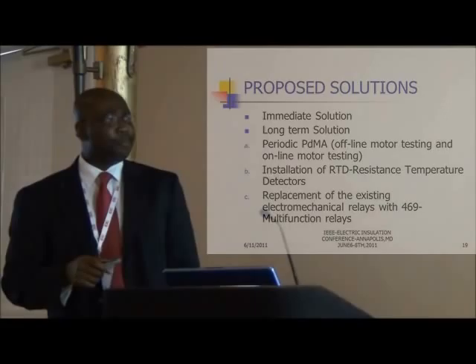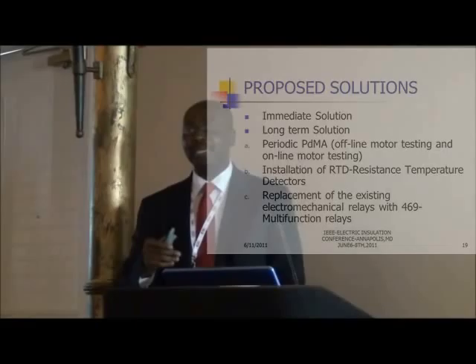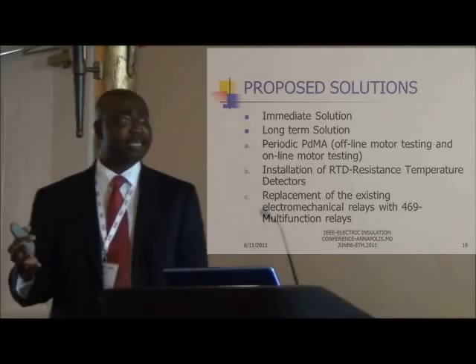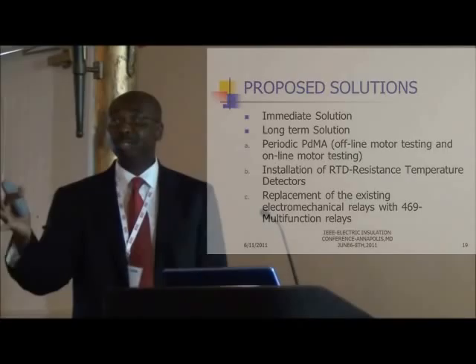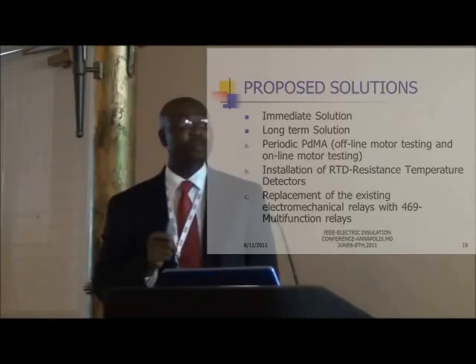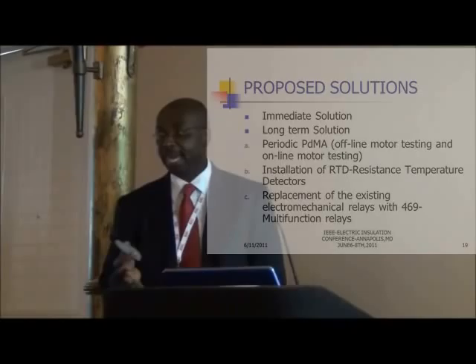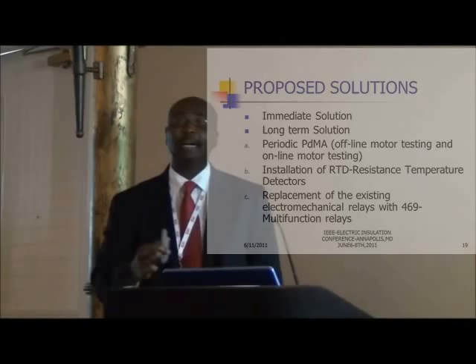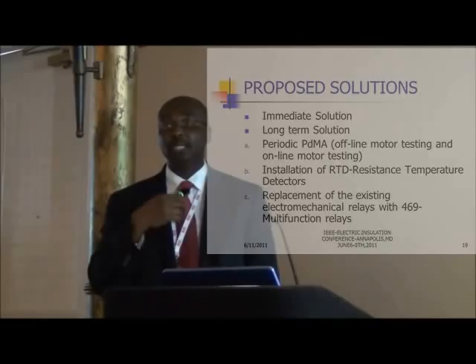The protection system for all these motors used electromechanical relays, which don't have multi-function capability. We came up with a proposal to replace all electromechanical relays with the GE 469 multi-function motor protection relay. This modern relay has the capability to monitor winding temperature in addition to overcurrent protection, and the temperature indication can be displayed in the control room.